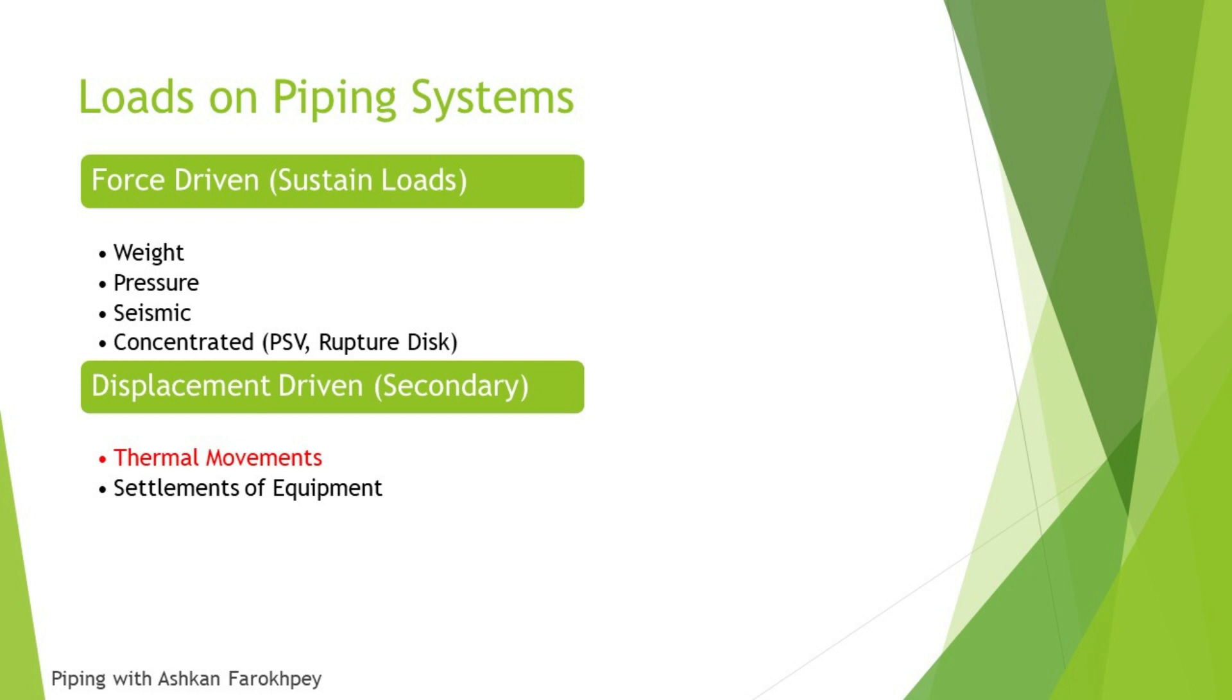As you know, we have two main types of loads on piping systems. The first group is the force-driven loads which we know as sustain loads. They can be listed as weight, the loads that come from the weight of the piping system, the pressure which is mostly the internal pressure that comes from the fluid passing through our piping system, the seismic loads that come from earthquakes and movements from earth or wind.